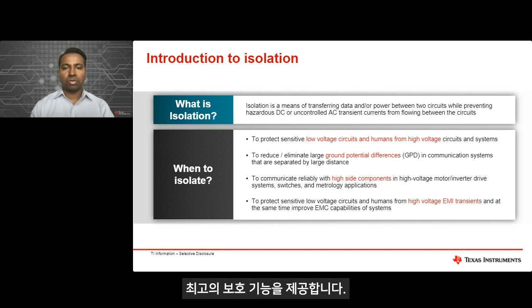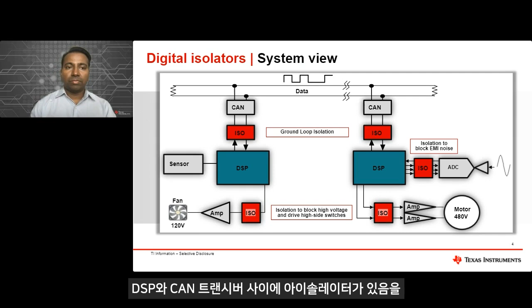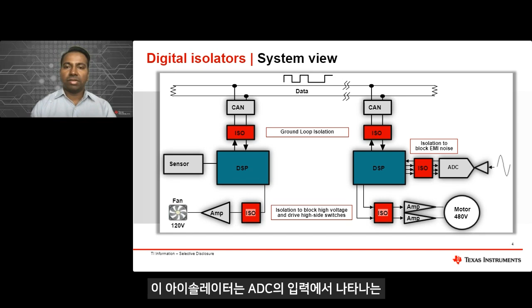Here is a system view of how digital isolators are used in a system. You can see that there's an isolator between DSP and CAN transceiver. This is an isolator to provide ground loop isolation, which minimizes or eliminates the ground potential difference that can happen between two communication nodes. There is isolation between DSP and fan, and also between DSP and a motor, and these are used to drive a high side switch and also block high voltage from the fan or the motor reaching the DSP. The isolation here is for both purposes. And then there is an isolator between DSP and ADC. This isolator is to block the EMI noise that is appearing at the input of the ADC.